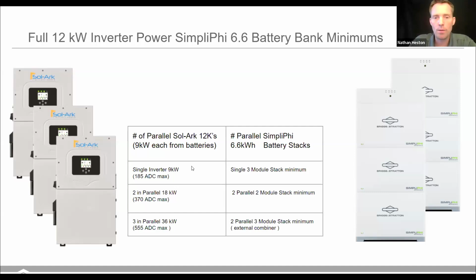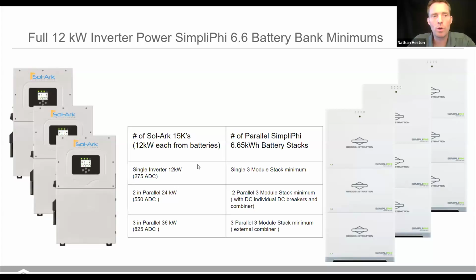If you have two 12Ks in parallel, you would want to have dual two stacks minimum, and then 3 12Ks in parallel. Maybe you're doing that three-phase power, for instance. You could do this with 2 3 stacks. Similarly, on the 15K, essentially one 15K inverter, 1 3 stack minimum, right? In order to be able to hit that full power output of that Sol-Ark 15K. And so 1-to-1 on the 15Ks, and on the stacks, these stacks are specifically designed to match that 15K Sol-Ark's power needs.